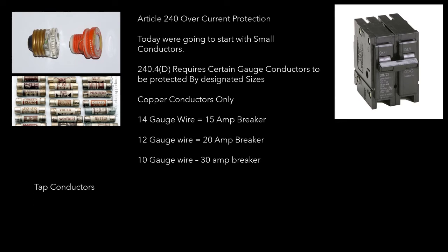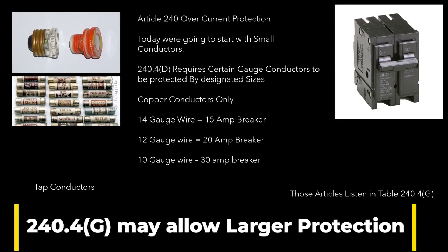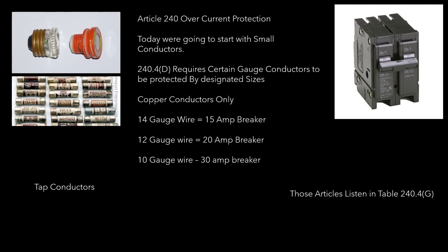Now let's talk about some of those exceptions. Tap conductors are one exception that may or may not allow you to put them on a larger breaker. The other exception is anything listed in Table 240.4(G), which includes air conditioners, motors, and other applications. For those, you go to that specific article and follow that article's prescription for sizing overcurrent protection, which may or may not allow you to go larger than prescribed here. So remember: 14 gauge wire — 15 amp breaker; 12 gauge wire — 20 amp breaker; 10 gauge wire — 30 amp breaker.